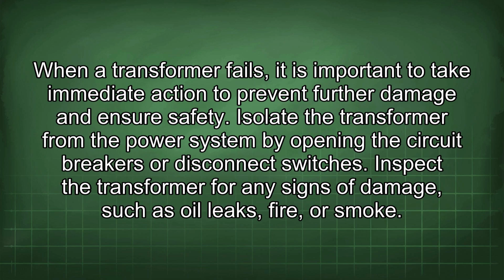When a transformer fails, it is important to take immediate action to prevent further damage and ensure safety. Isolate the transformer from the power system by opening the circuit breakers or disconnect switches. Inspect the transformer for any signs of damage such as oil leaks, fire, or smoke.